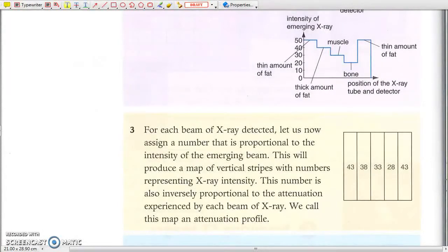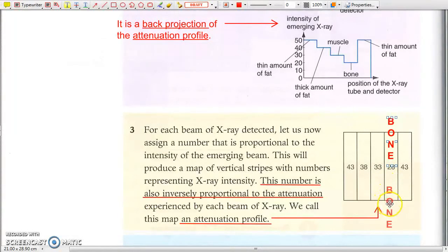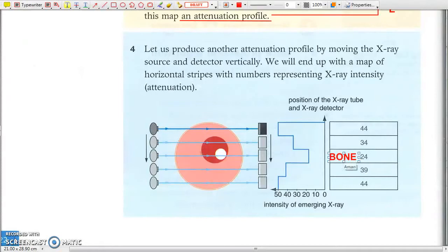The transmitted intensity variation is called a back projection of the attenuation profile, or simply an attenuation profile, as these numbers are inversely proportional to the attenuation experienced by each beam of the X-ray. We may then start to locate the high attenuation tissues, such as bone, where at which Y position the bone is located. Then the X-ray beams from a perpendicular direction may form another attenuation profile, from which we can also locate the high attenuation tissues.